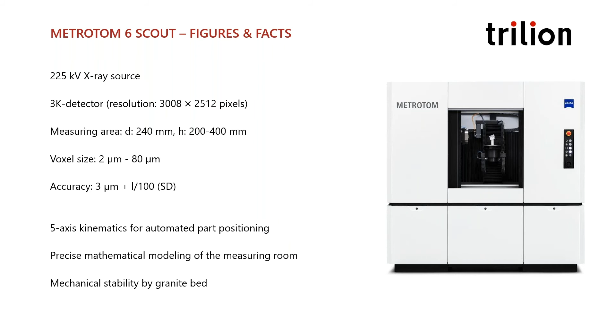VDI tests. So if we take a look here, this is actually another model of the inside of our Metrotom 6 Scout. Basically, this can give you an idea of which parts will fit inside your CT. When we look at voxel sizes, you see here, this is basically a 3D pixel, so this is equivalent to your resolution. Long story short, we work with the principle of magnification to increase resolution.